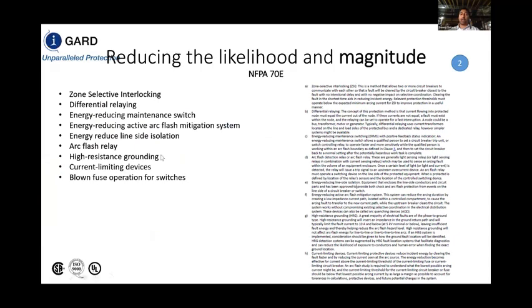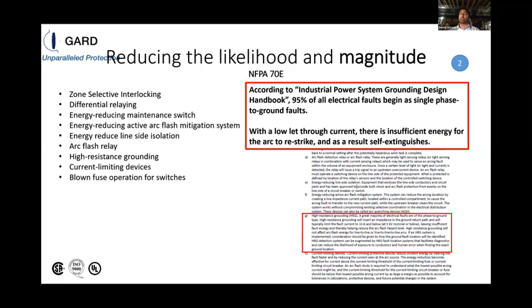Of the 9 that are listed, high resistance grounding is the only one that's reducing the likelihood. All of the other incident energy reduction methods are acting after the fact that the arc is already in the system. So for high resistance grounding, we know that if it's a phase to ground fault, we're limiting that fault current's magnitude to a specific value. And we know that 95% of electrical faults begin as single phase to ground faults. So when we select a low enough let through current, there's insufficient energy for the arc to restrike, and as a result, it self-extinguishes. The only issue with resistance grounding is the phase-to-phase and phase-to-phase-to-phase failures where our neutral grounding resistor is no longer able to limit the fault current. So although HRG is able to reduce the likelihood, it can't reduce the magnitude because the magnitude is also taking into consideration phase-to-phase and phase-to-phase-to-phase failures that are occurring in the system.